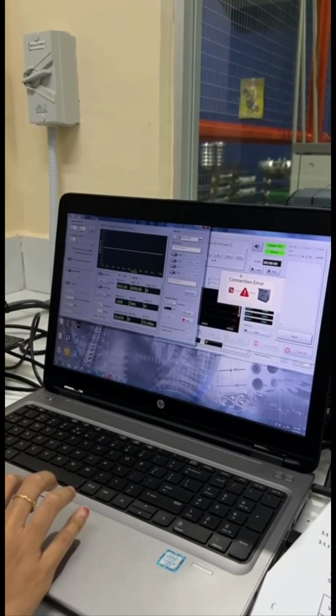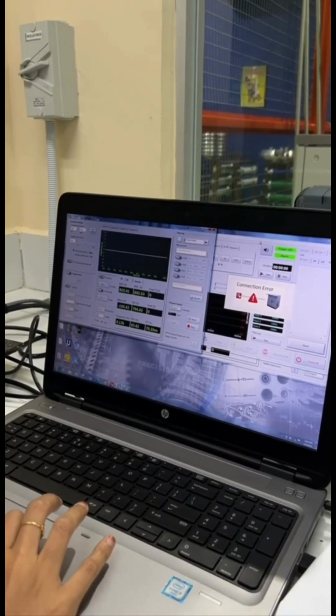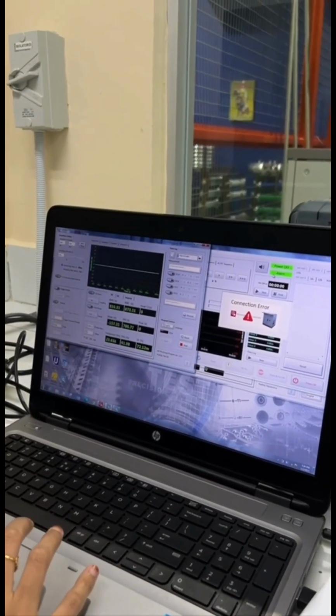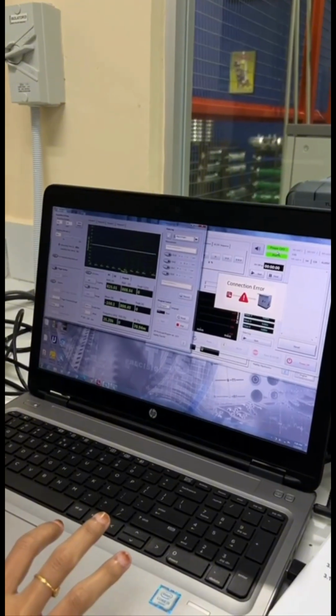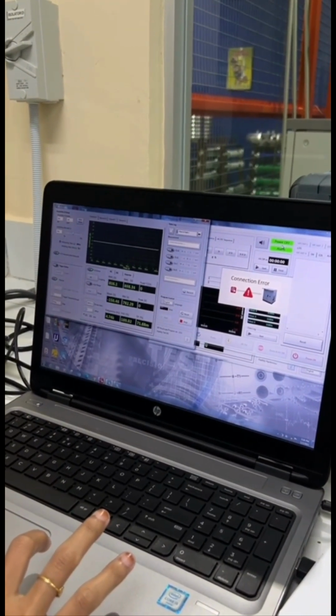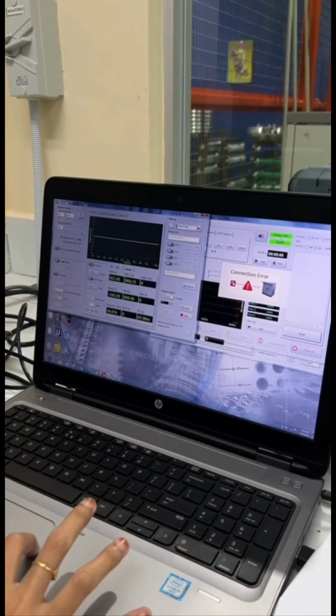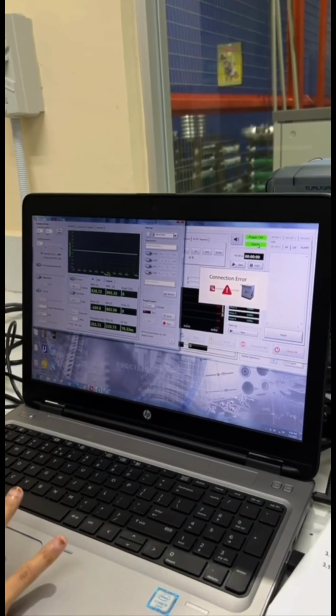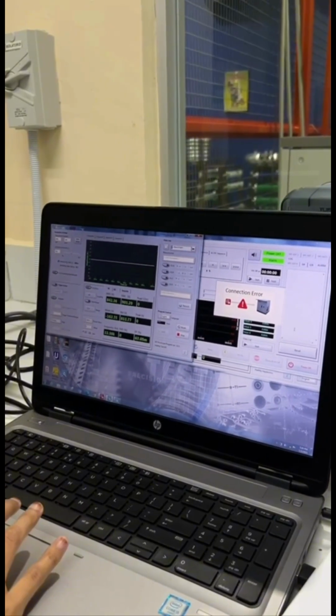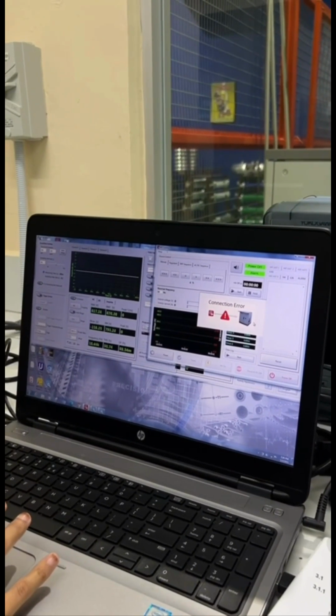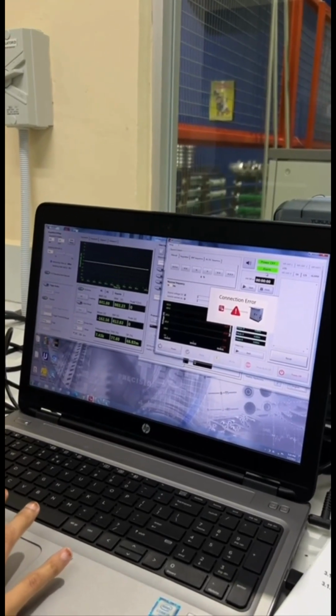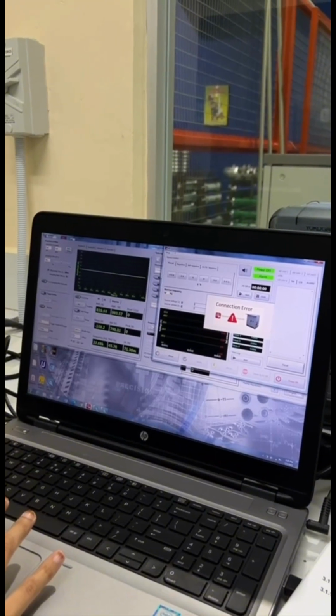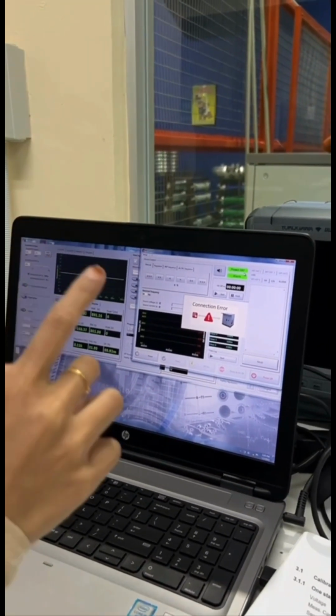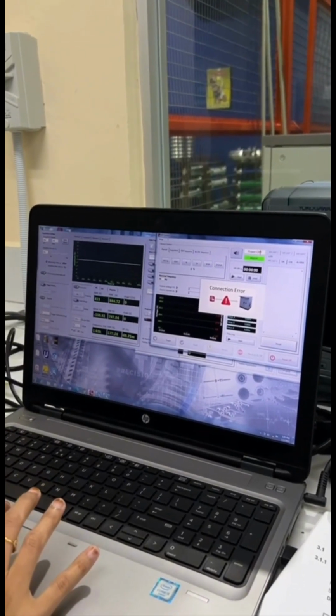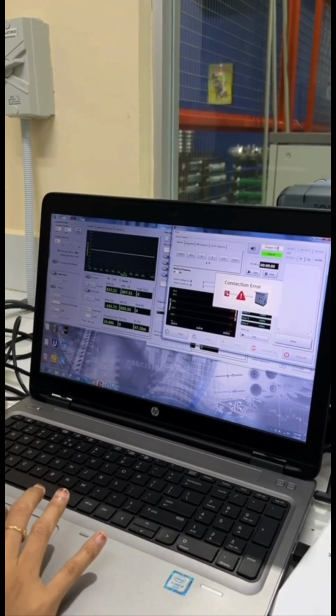Okay, done. First, open the kit application and perform the customer setup. During the setup, select channel 3 or channel 4 as both correspond to VM2 output, which is used for AC. After completing the setup, assign the required value to channel 4. Then navigate to the alarm section. In this section, all errors related to the operation will be displayed. Reset all existing errors first. Once the reset is complete, the power button will change to power on, indicating that the FC converter is ready for injection. When the power on button is pressed, the FC converter will begin the injection process.